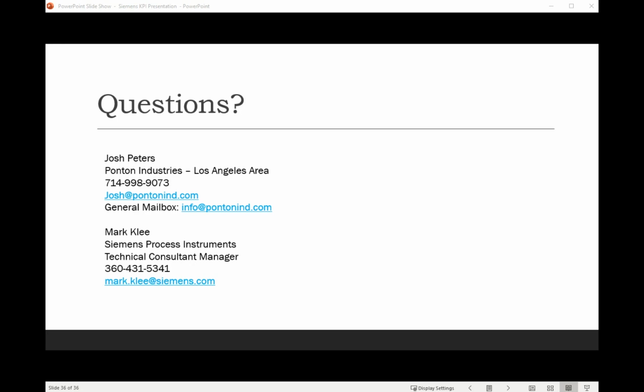Yeah, I would say why not both? In any level application, a point level measurement really is critical to have a critical high or low, especially if it's something where you have an overflow condition. And generally you want to use a different technology for your safety system than you do for your main measurement. A Pointek is only going to be a contact closure or a relay closure to say, I have reached a level, pick a number, at 10 feet, right? And so it's only going to give you an indication when you get there. The Hydroranger is going to give you an analog measure, so I can see I'm at 6 feet, 6.5 feet, 7 feet, 8 feet, 9 feet, and so on.